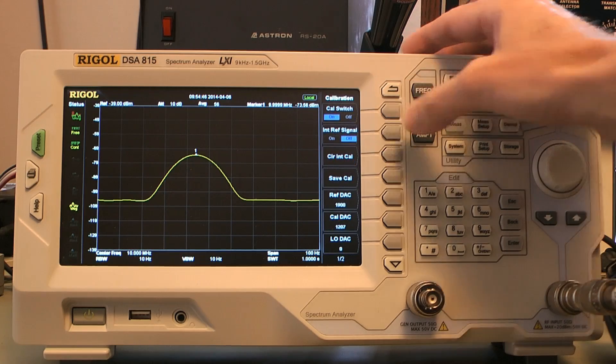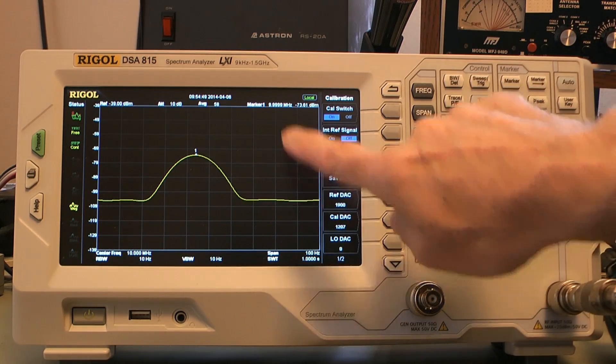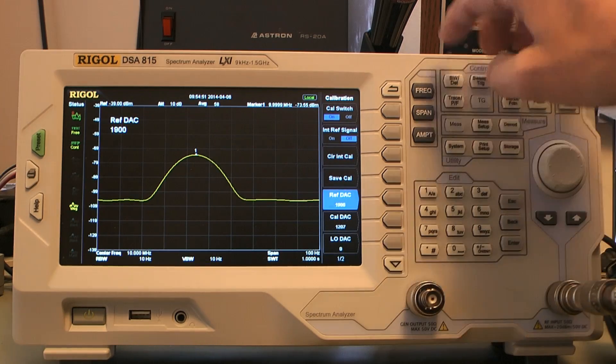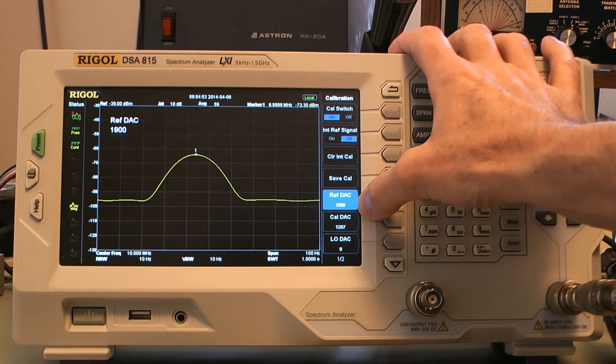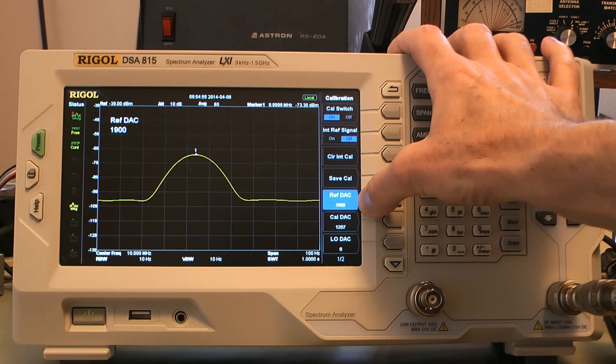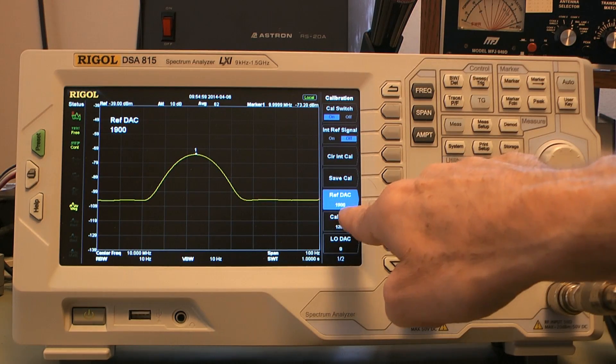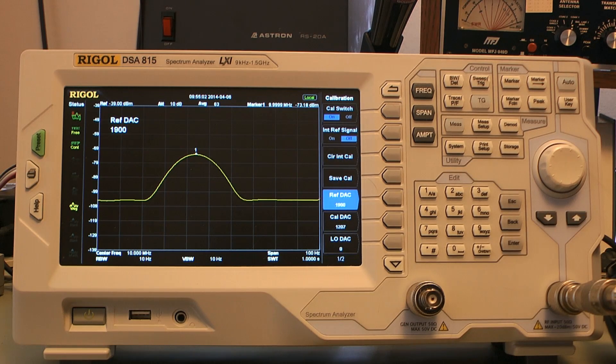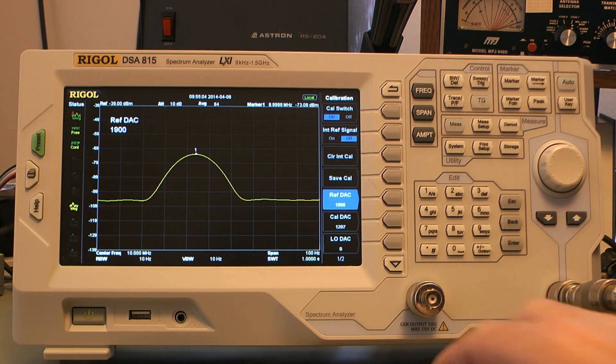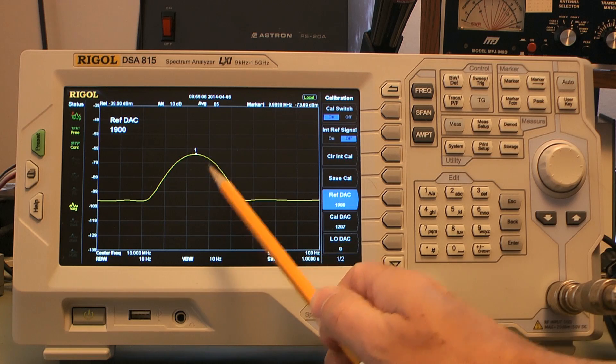And the one that we want for frequency is ref DAC. So the reference digital to analog converter is currently at 1900. I moved it there intentionally to move the signal off so that you can see that it is not at 10 megahertz.